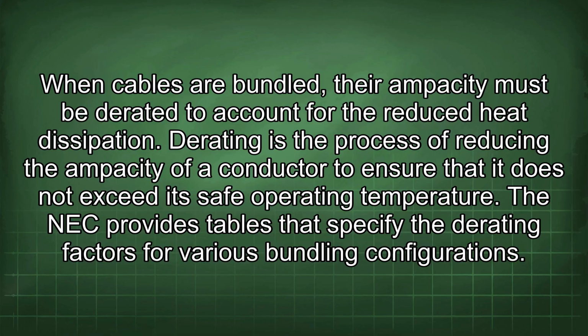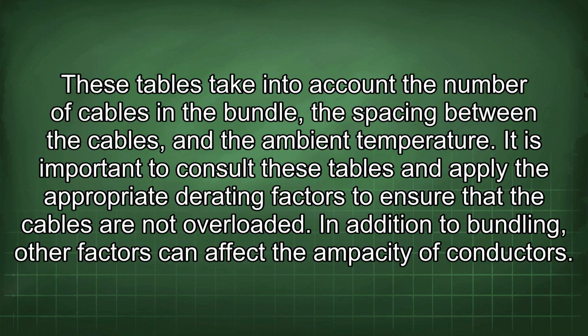Derating is the process of reducing the ampacity of a conductor to ensure that it does not exceed its safe operating temperature. The NEC provides tables that specify the derating factors for various bundling configurations. These tables take into account the number of cables in a bundle, the spacing between the cables, and the ambient temperature. It is important to consult these tables and apply the appropriate derating factors to ensure that the cables are not overloaded. In addition to bundling, other factors can affect the ampacity of conductors.